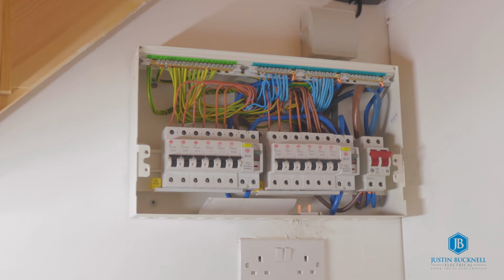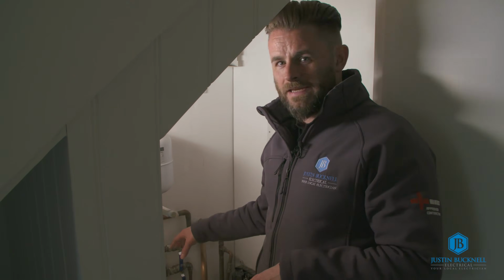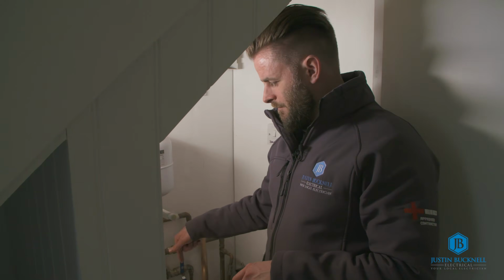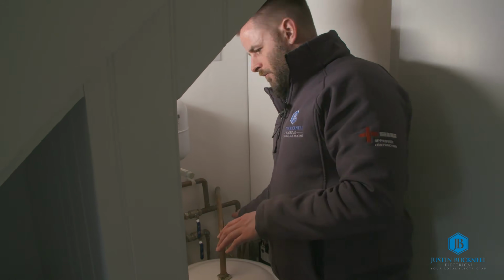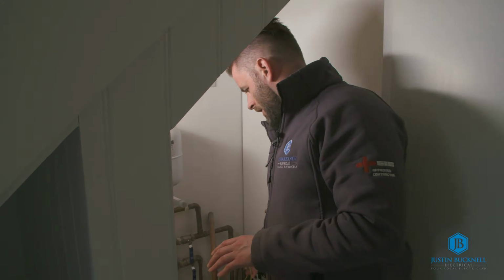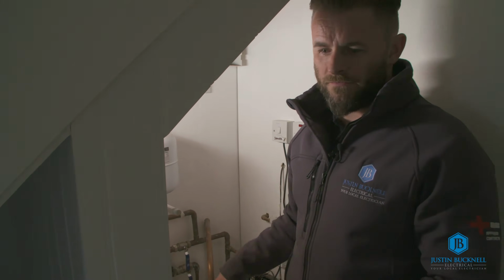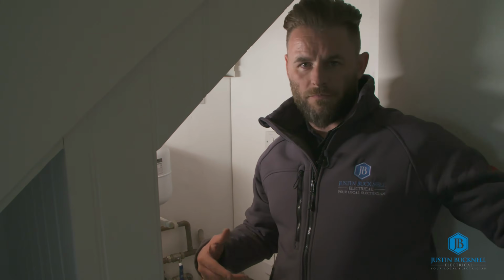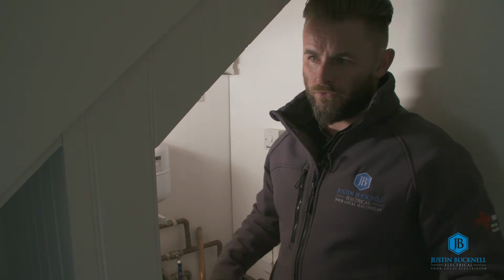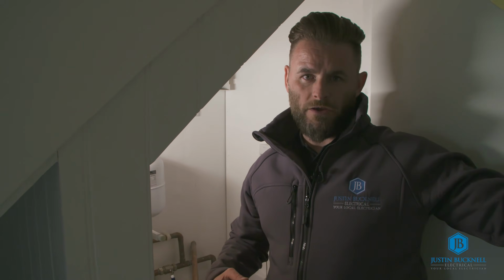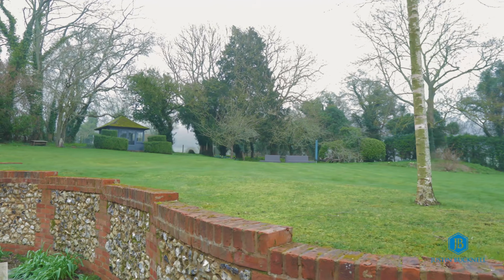So we have a similar situation here with the bonding for the main water supply coming into this annex. It does actually come in a blue plastic pipe again, but they've run in an earth cable and not connected it. However, down in this corner, we can see metal pipe work go into the fabric of the floor, and then they re-emerge elsewhere. So we would have liked to see it bonded at the point of entry, and also where it re-emerges elsewhere out the floor in another part of the annex.